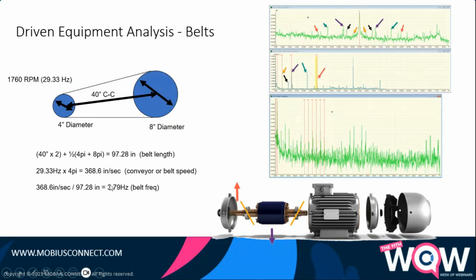So we take a look at it, 3.79. And then you can see here are the frequencies from that application. There's some bearing peaks, there's some belt peaks, some misalignment peaks, and then some other bearing peaks. And then, of course, if I've overtensioned the belts, I get static eccentricity. For those involved in vibration, static eccentricity results in something called unbalanced magnetic pull. So that unbalanced magnetic pull is also an energy loss.